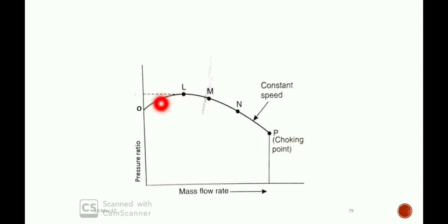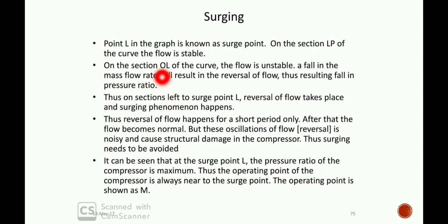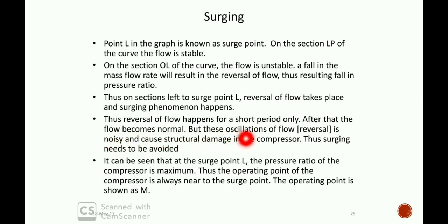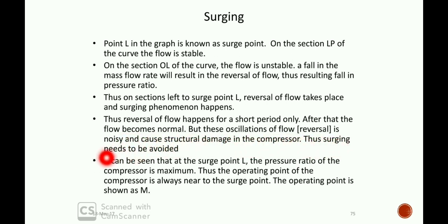On the section to the left of surge point L, the flow is unstable due to surging. A fall in mass flow rate will result in reversal of flow, thus resulting in a fall in pressure ratio. To the left of surge point L, reversal of flow takes place and the surging phenomenon happens. The reversal of flow happens for a short period only, after which the flow becomes normal again, but these oscillations are noisy and cause structural damage.